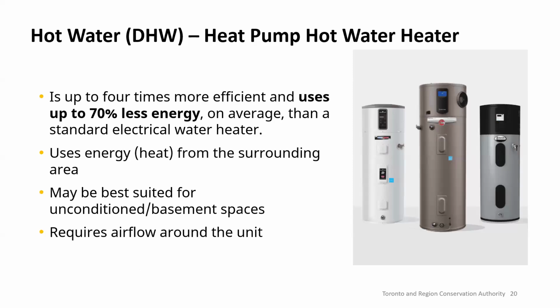One slide here on heat pump hot water heaters—these are pretty nifty. They look like standard old hot water tanks, but if you notice, they have weird doohickeys, odd sections on top. In the middle unit pictured on the right, you can see a little circle—there's actually a fan behind there, and a little mini air-to-water heat pump inside that heat pump hot water heater.